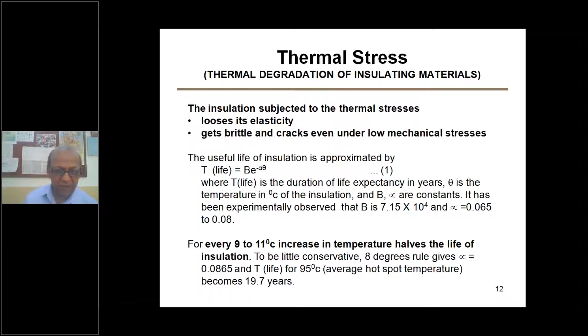Now you see this, if you increase the temperature by 1 degree, the life of the transformer is reduced by 1.6 years. So that is also a very important thing to remember. Then rural distribution transformers are exposed to direct sunlight, that is a 10 to 25 degree extra temperature rise when the sun is there, and we have sun on quite many days in our country.